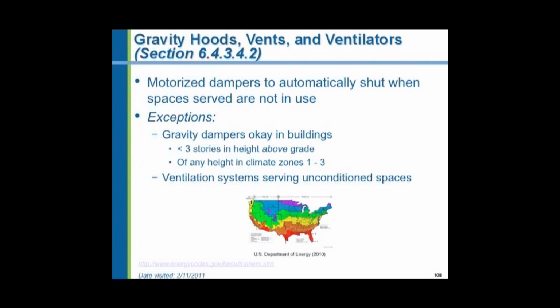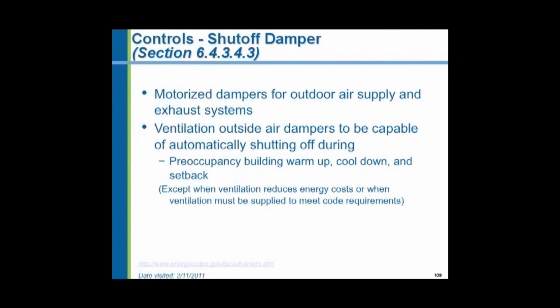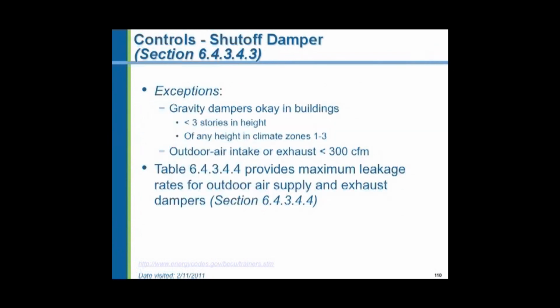Gravity dampers are okay in the lower climate zones 1 through 3, and in short buildings. Ventilation dampers, dampers bringing outside air into the building for breathing purposes, have to be shut down when the building is not occupied, or when the building is coming up to temperature in the winter or down to temperature in the summer. They want full recirculation in the building. An exception is when you're actually using the outside air to help cool the building in the pre-dawn hours. Again, the shut-off dampers and the damper leakage rates are specified. They have to seal tightly with maximum leakage rates as specified in the code.